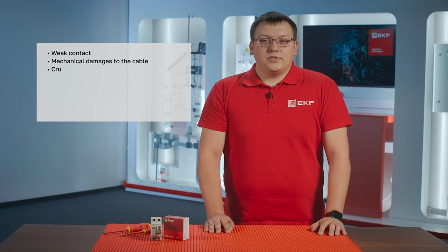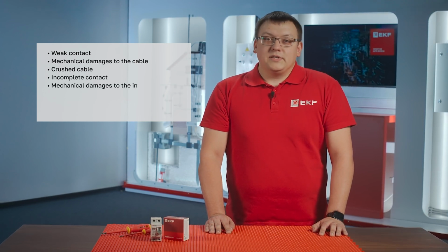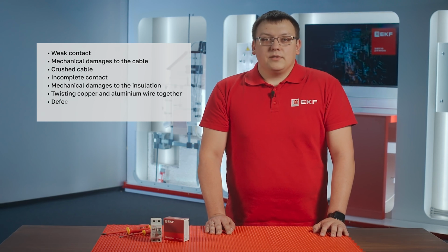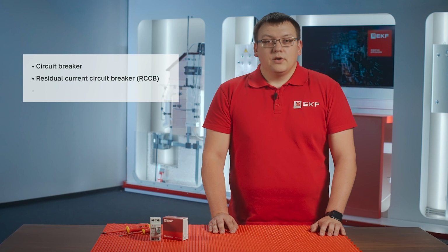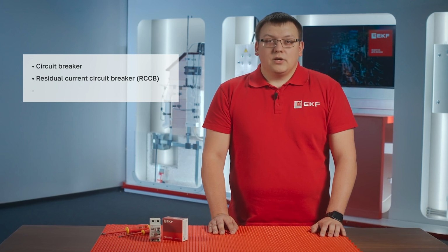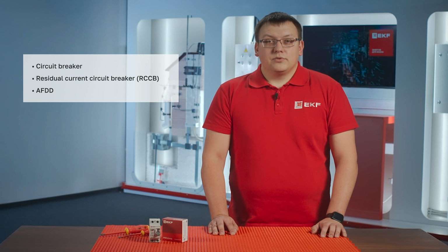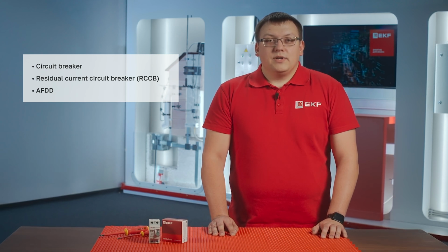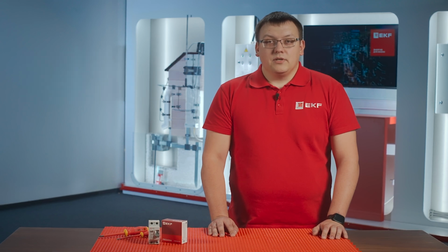Other reasons for a fire may include weak contact, mechanical damage to the wire or insulation, for example, when drilling a wall, twisting copper and aluminum wire together, or aging of insulation. To prevent the primary causes of fire we've discussed above, we must create a multi-level fire protection system that includes: first stage, a circuit breaker that protects against short circuit and overcurrent. Second stage, a residual current circuit breaker that protects against ground leakage current. Third stage, AFDD protecting against short circuit and overload if it's an AFDD combined with a circuit breaker, a parallel phase to neutral or phase to ground arc fault, and a series arc fault.